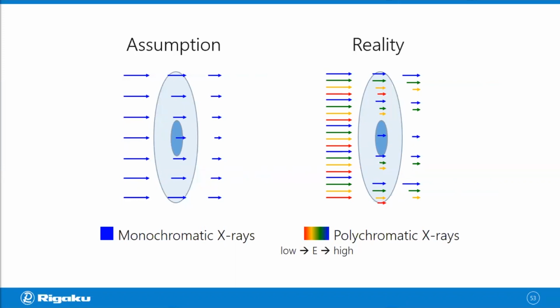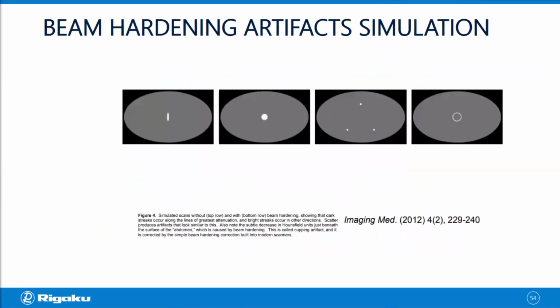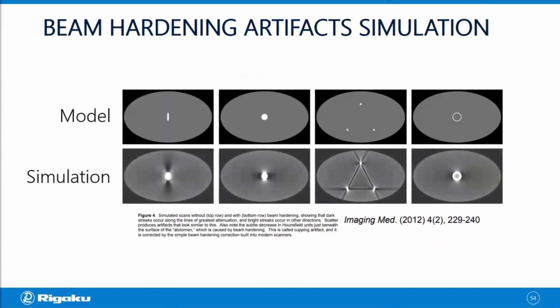But it is important to know what they look like so that when you see one, you would recognize it as an artifact. So those four cross sections are models we're going to use to do X-ray CT simulation. And the white areas represent high density areas that can often cause beam hardening artifacts. If you do CT scan for those cross sections, you're going to get something like those. You can see that the model and the simulation look different, and that's because the simulation has artifacts, like those streaks coming from the high density areas. It gets worse when you have multiple high density areas, and you see shading like this one sometimes as well. So this is how beam hardening artifacts usually look like.